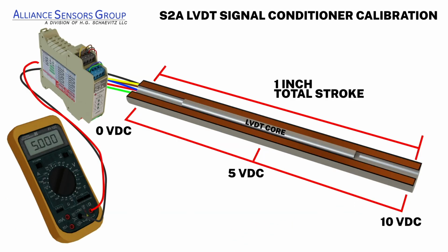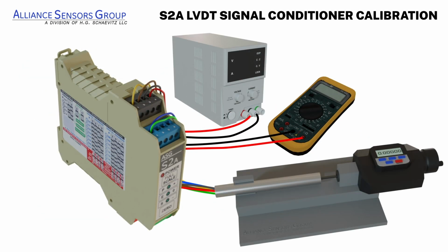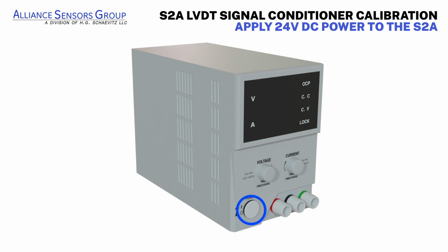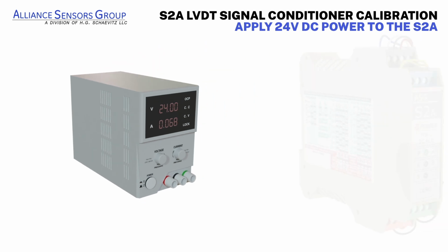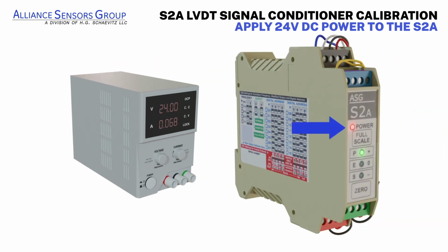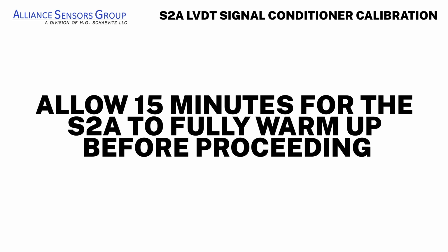Now with all the connections made and the LVDT positioned into the test fixture, we will apply 24 volts DC power to the S2A. The red power LED on the face of the unit will illuminate, indicating power is present. The green P LED will illuminate as well, indicating that the S2A is operating as a standalone master. It is important to allow 15 minutes for the S2A to fully warm up before proceeding with calibration.